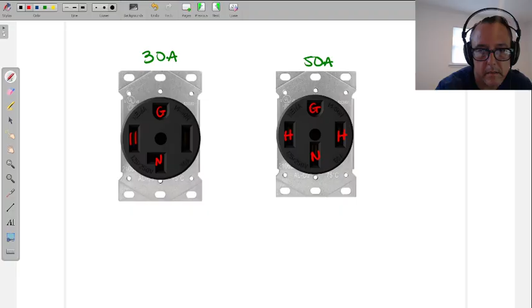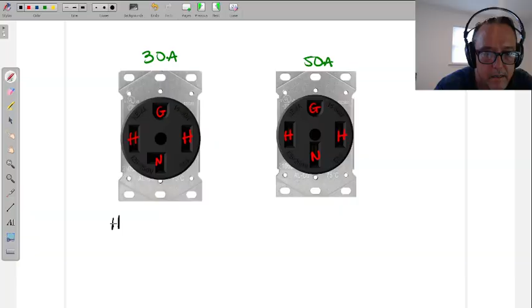Now, very important that you do a double check on one of these. If you're at a breaker, it's impossible for what I'm going to show you to happen here. Again, at a breaker, this could never be the case. But at an outlet, because somebody ran wires to this, and I don't know what these wires are because it's behind concealed stuff, I want to do a hot to, let's just say, ground, or actually neutral.